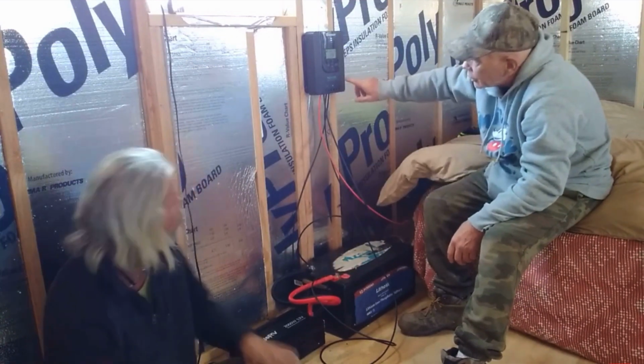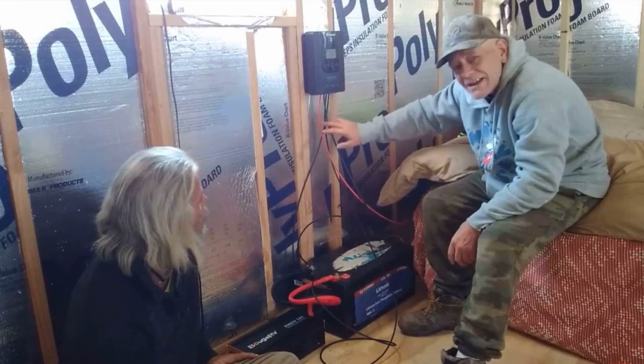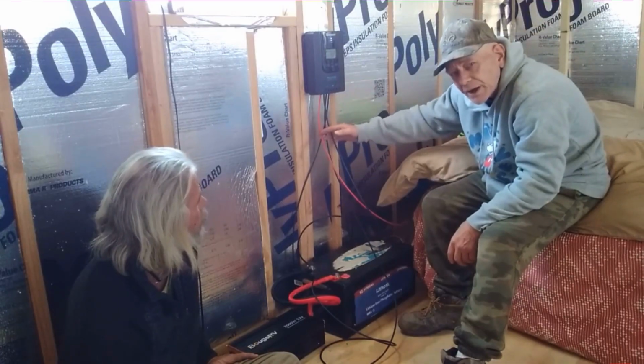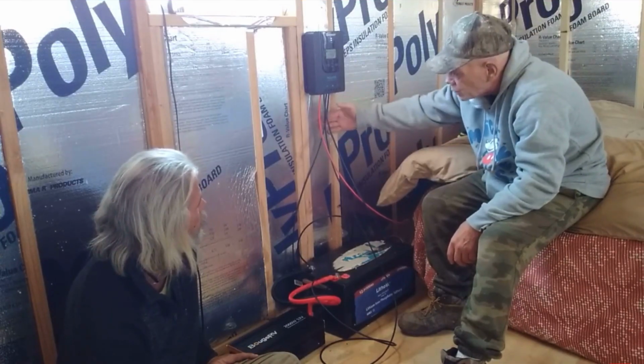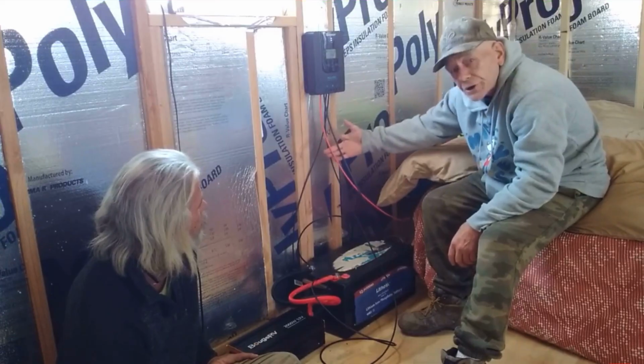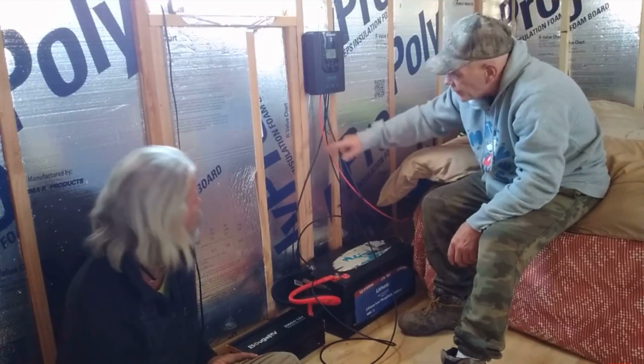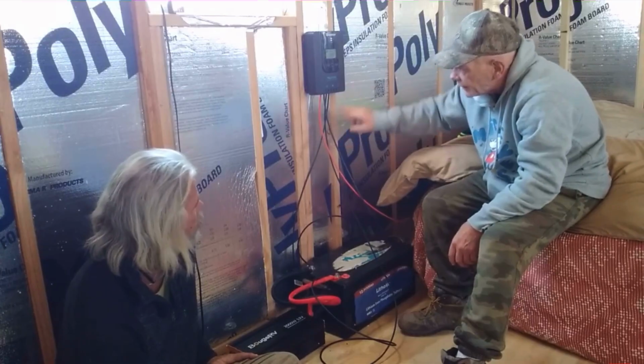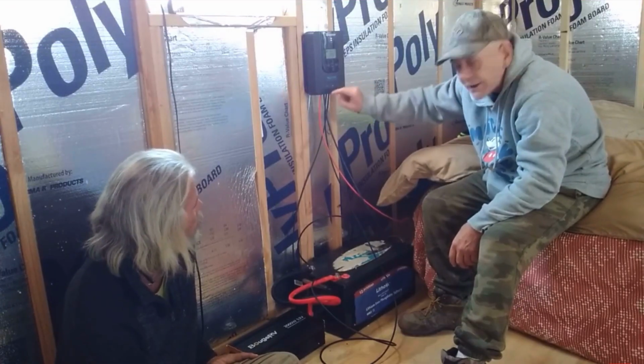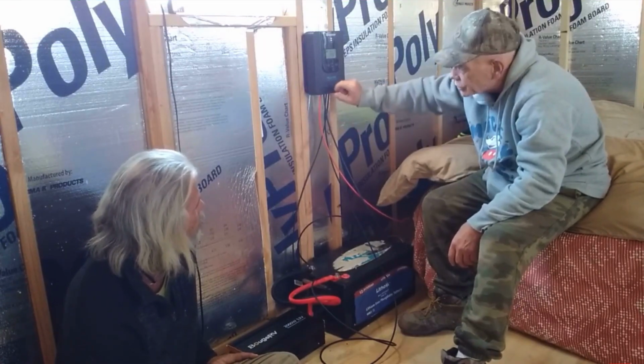From the controller, we have 4 8-gauge wires, which is what's recommended by the manufacturer. These are 8-gauge wires going in. These 2 wires are coming from the solar panels - we've got a red positive and a black negative. They go into the left side in here. You slide them up into the slots, and then you screw down the screws.